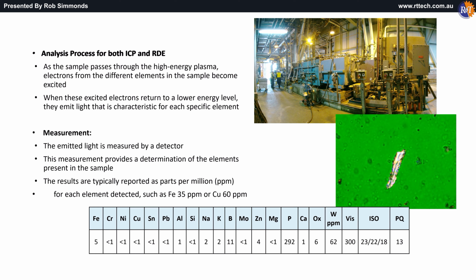Analysis process for both inductively coupled plasma and rotating disc electrode spectrographic. As the sample passes through the high energy plasma, electrons from the different elements in the sample become excited. When these excited electrons return to a lower level, they emit the light that is characteristic for each specific element. The emitted light is measured by a detector. This measurement provides a determination of the elements present in the sample. The results are typically reported as parts per million, ppm, for each element detected, such as Fe 35 or copper 60 ppm.